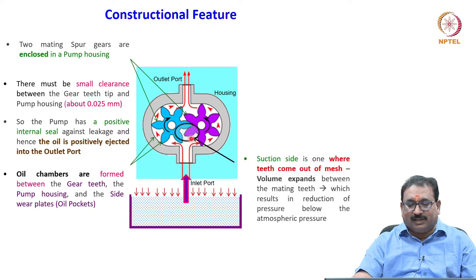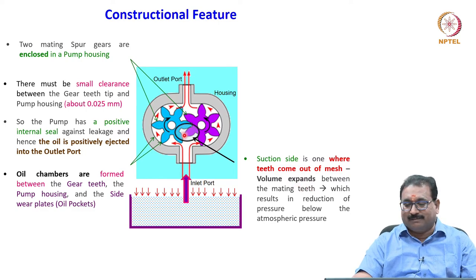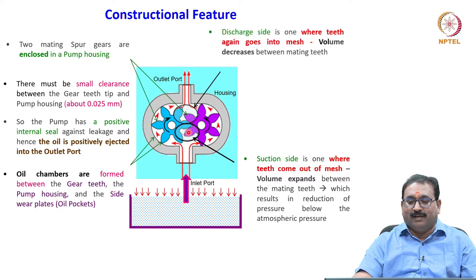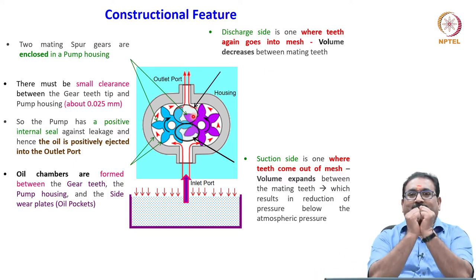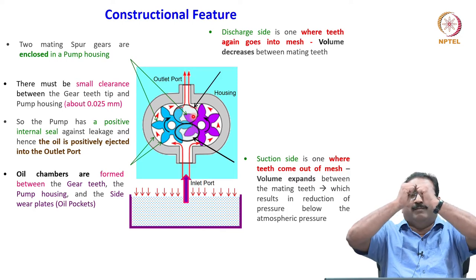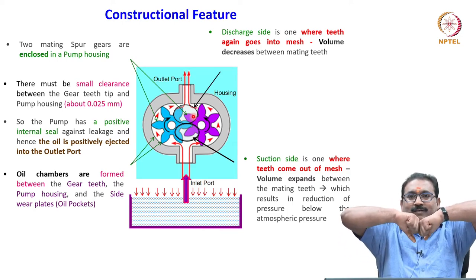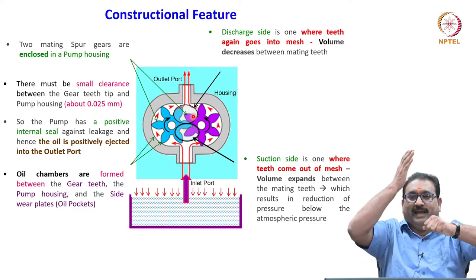The suction side is where teeth come out of mesh — volume expands between the mating teeth, which results in reduction of pressure below atmospheric pressure. The discharge side is where the teeth go back into mesh — volume decreases — and the oil is ejected. When the gear unmeshes, vacuum is created and it sucks due to the differential pressure.